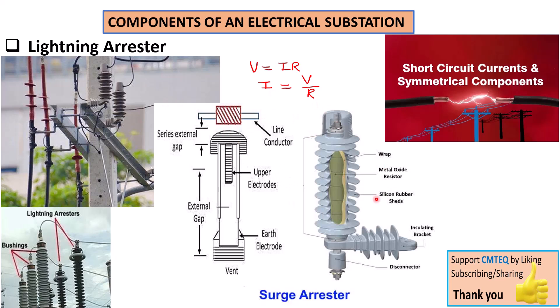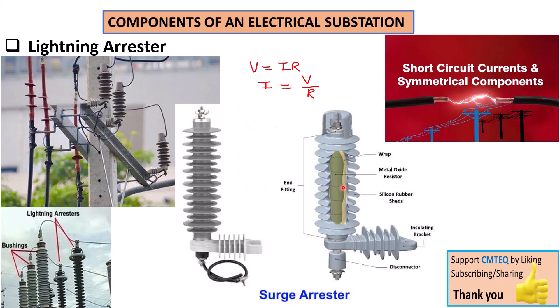The other type of lightning arrester, shown here on our screen, is based on the metal oxide resistor. This resistor is a non-linear resistor inserted internally in this lightning arrester. This non-linear resistor basically means that when the voltage increases, the resistance also decreases. By the way, this is the same operation as an MOV — metal oxide varistor — which is very widely used in electronic circuits. We're going to look at that in a moment.